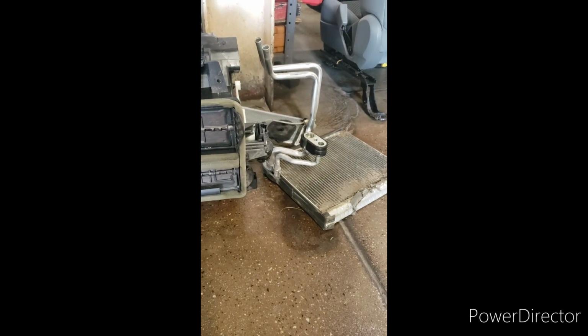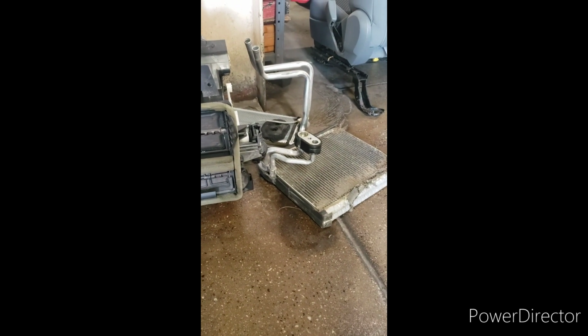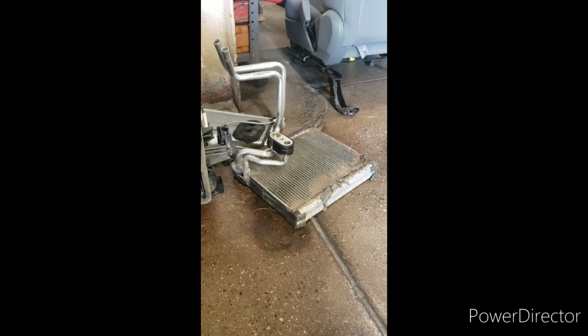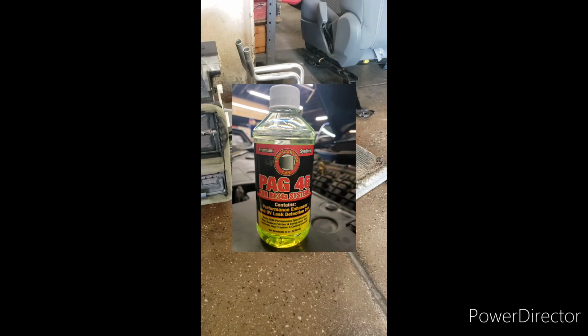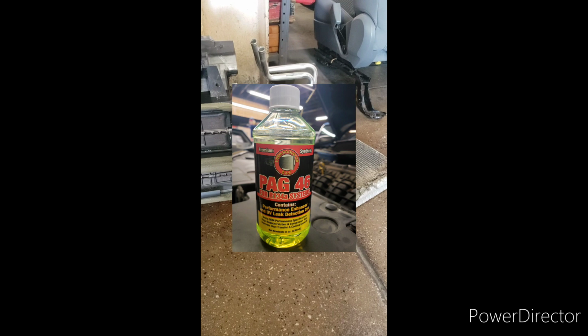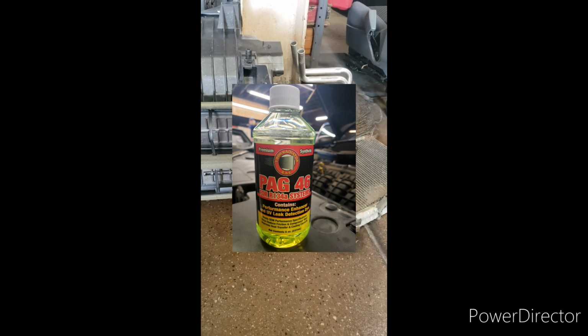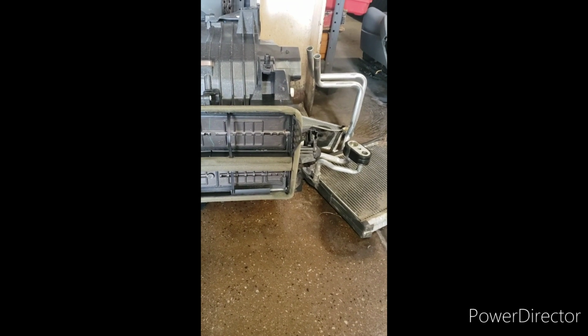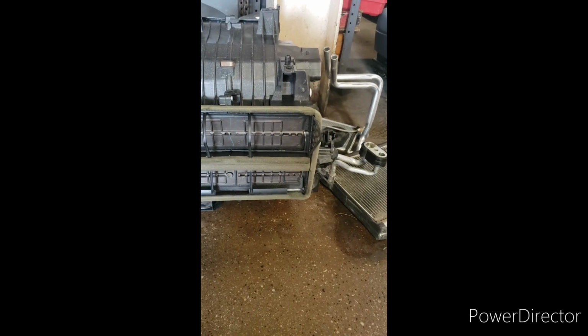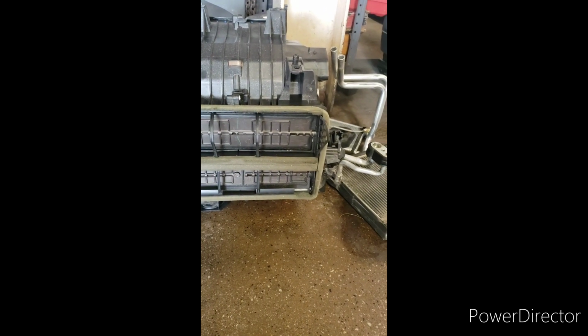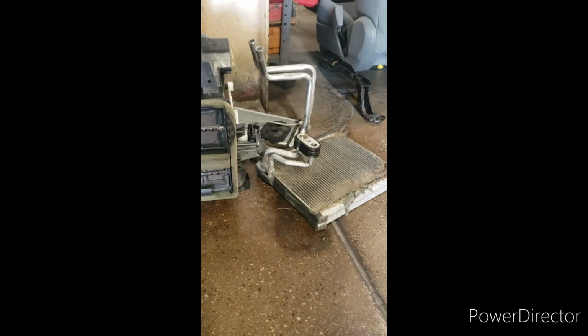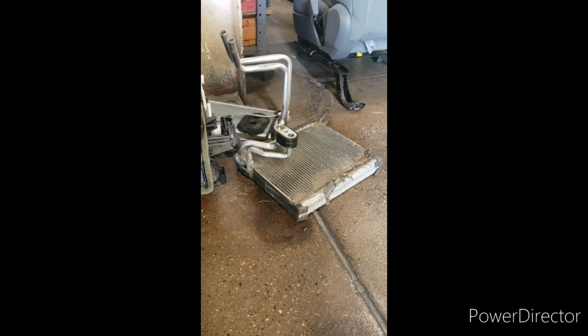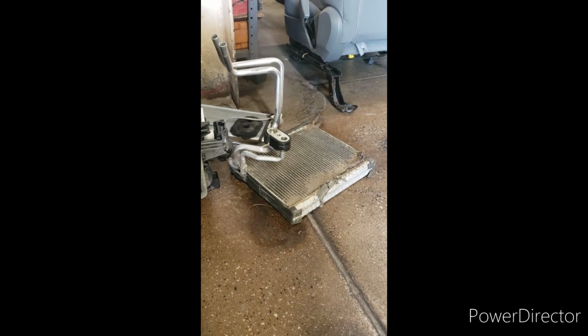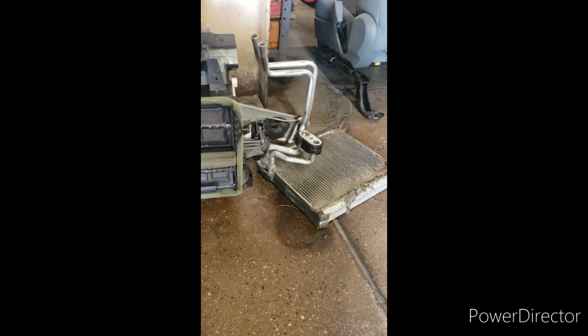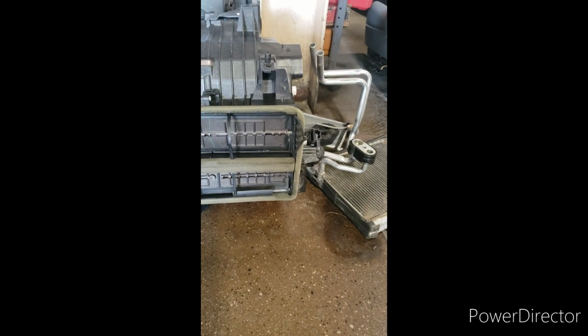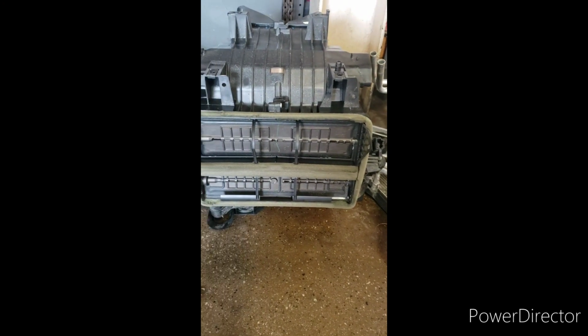I'm going to be adding a little less than a quarter ounce of PAG 46 to the new evaporator. My machine showed that I pulled out about a quarter of an ounce of oil when it was out of Freon. Oil balancing is crucial. Not enough oil is catastrophic to the compressor, but too much oil causes higher vent temperatures. So guys, you want to make sure the oil is balanced properly.